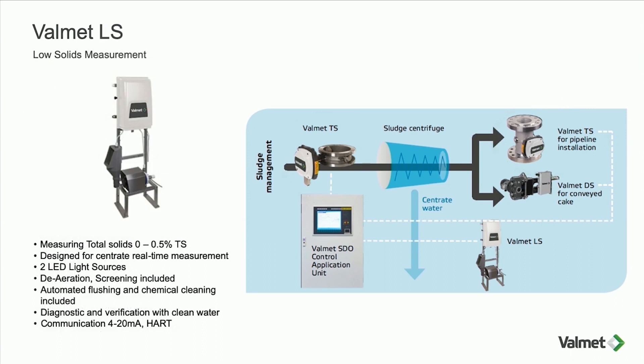The second technology is Valmet LS, designed specifically to measure from the centrate area of the centrifuge — measuring the filtrate coming from the bottom of the centrifuge. We can measure up to 0.5 percent total solids here. It uses an optical measurement method with LED light sources giving three different light phenomena: backscattering, absorption, and depolarization. Those three combined signals give a good calibration against centrate.